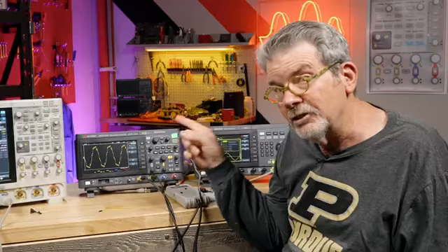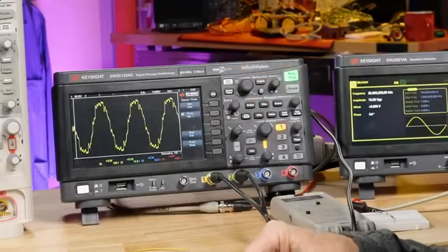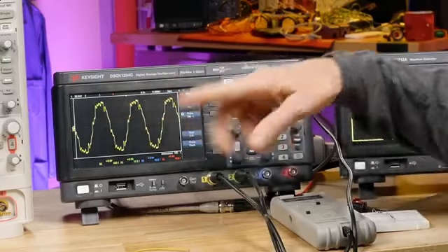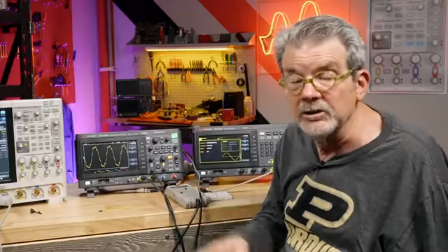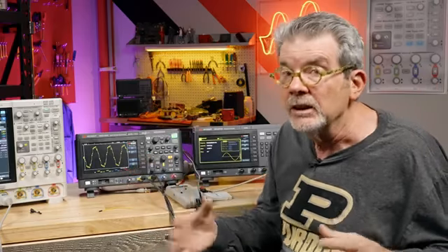This is the AC input in this room. It is really ugly. Look at all that interference or garbage riding on that sine wave. I've seen it in this building before. I did this test at home yesterday. I had a pretty clean sine wave in my home lab. But in this factory, there's lots and lots of equipment connected to the grid, and it can cause interference on the grid, and I think that's what we're seeing here.